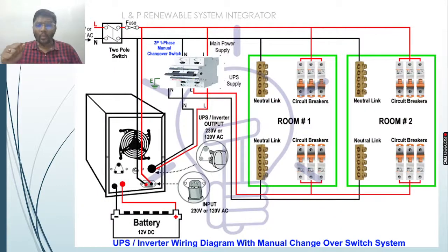Now for the last model, when you want to make inverter wiring along with a manual changeover switch, you can follow this wiring. This is the main supply. From the main supply we connect the line and neutral to the 2-pole single phase manual changeover switch.